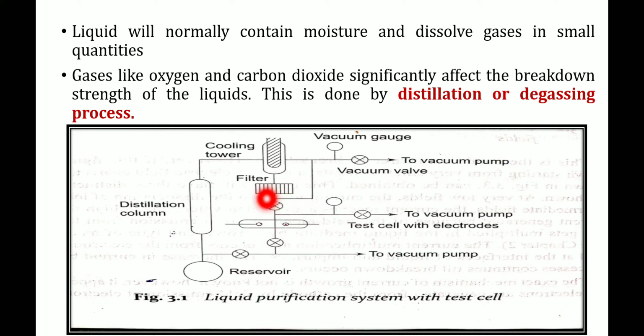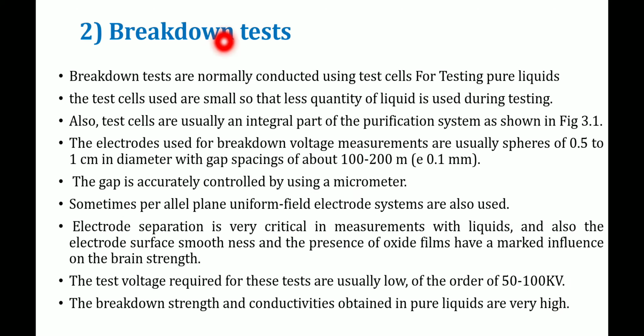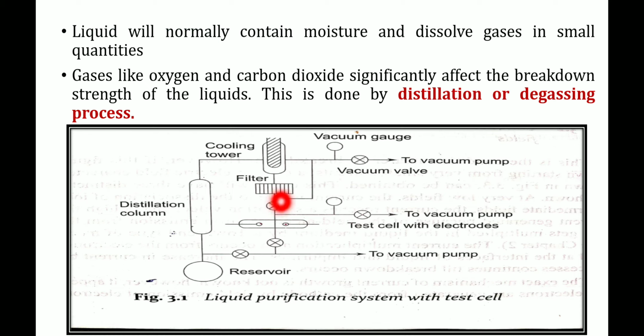A sample of the pure oil, nothing but impurity-free oil, is taken in the test cell itself. This test cell consists of 2 electrodes, and it is mainly used for carrying out the breakdown strength test of an oil. That process I will explain with the help of a diagram. The sample of the oil is taken in a smaller test cell and filled in here. This test cell consists of 2 electrodes, with a small distance between them, and it is completely filled with the liquid or oil.